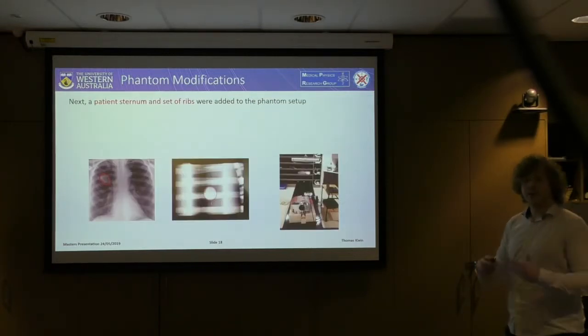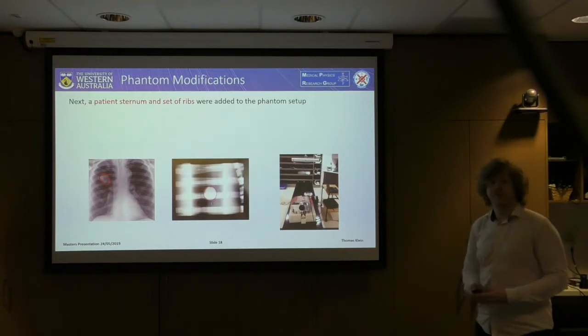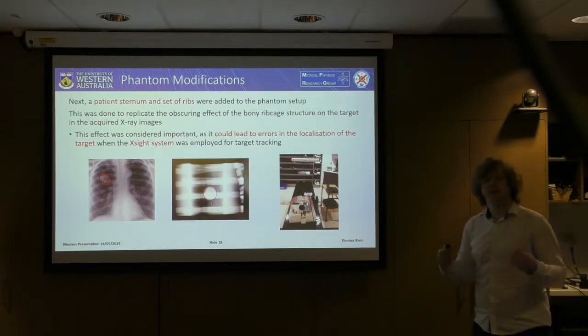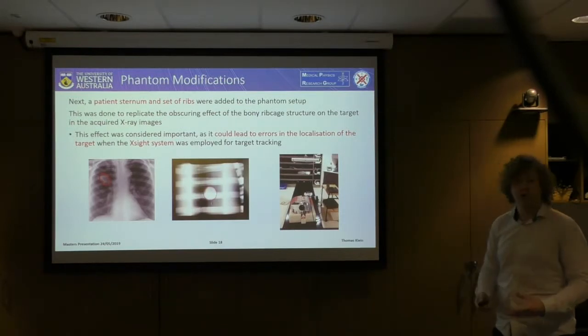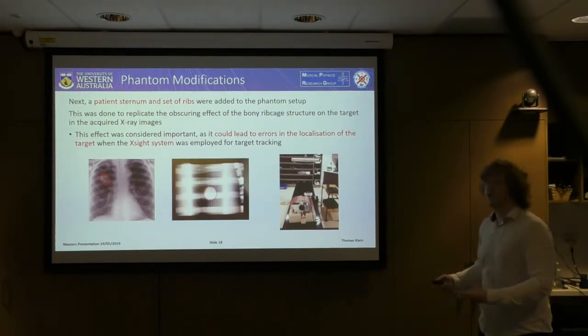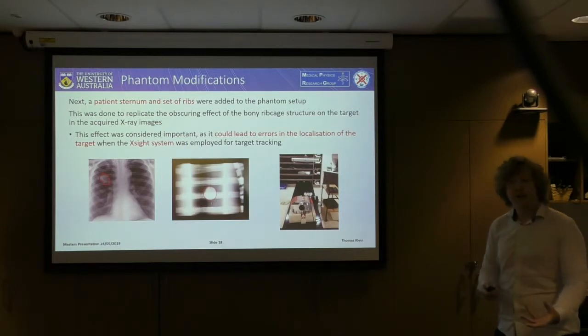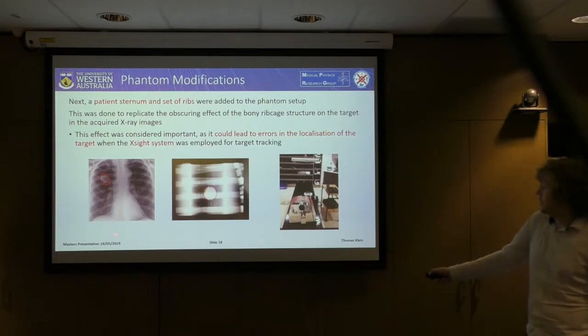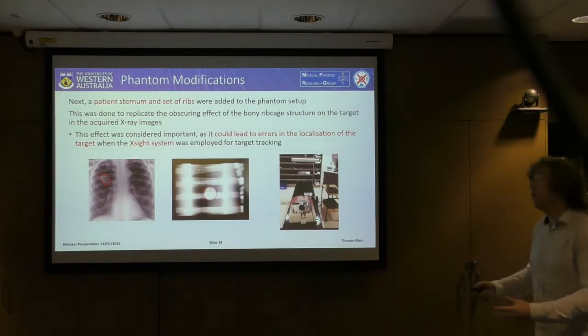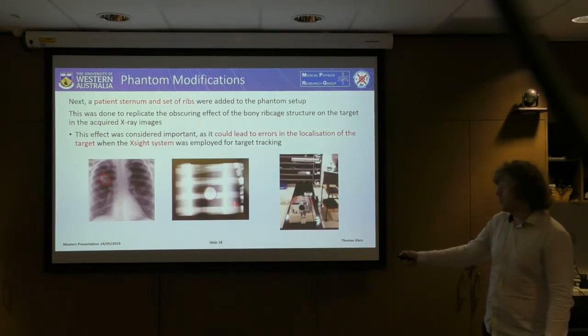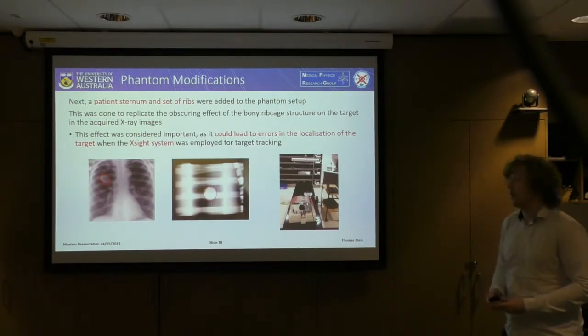We also needed to add a sternum and ribs to the lung phantom to replicate the obscuring effect of bony structures on the target. This is particularly important because it could lead to errors in the target tracking accuracy of the Xsight system as opposed to the fiducial-based system. This effect is illustrated for an anonymous patient CT scan where the ribs are obscuring the tumour from view, and we've tried to replicate this effect in our phantom images.